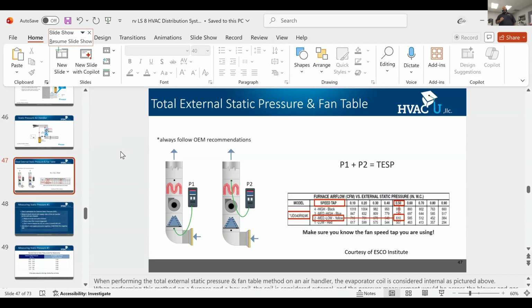We're looking to design it where the static pressure is modest. In some cases, it might be 0.7 because we're adding an evaporator. We sometimes have to design at 0.7 just so we have enough static pressure available to push the airflow throughout the duct system. If you look at tools like The Energy Conservatory's, the default settings, unless you change them, are often, I forget, either 0.7 or 0.8, or they'll start to consider that high. So that's a test pressure. That's what the furnace is tested at.